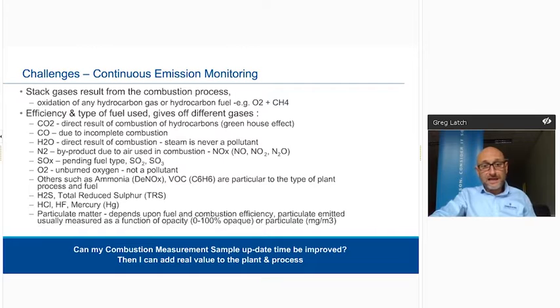N2 and all the components of that - it could be NO, for example, as an inferred value of NOx through converters, NOx converters, SOx, SO2 or other, and SO3, which is a horrible one. O2, obviously we want to have, if we can, a very low O2 level, so you do end up optimizing your process fuel as much as you can.